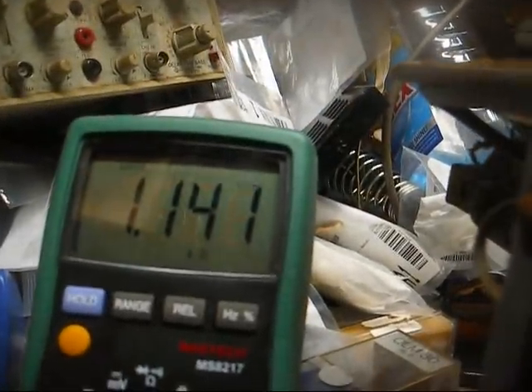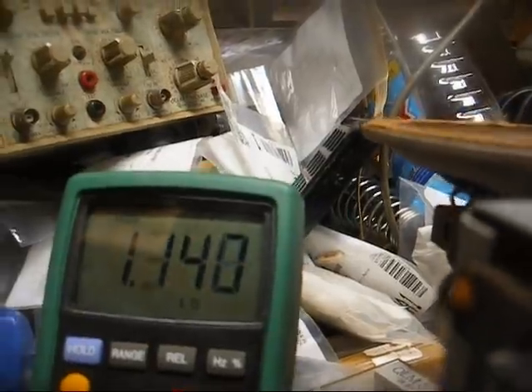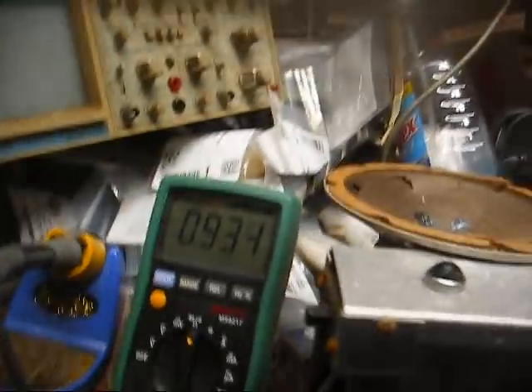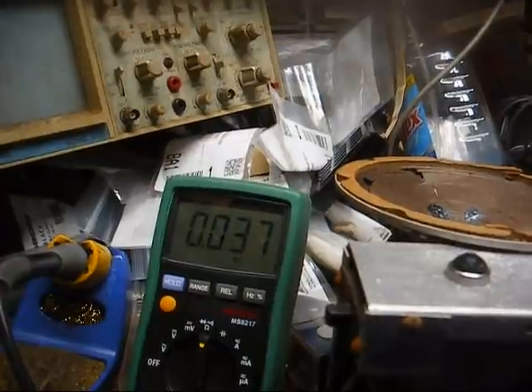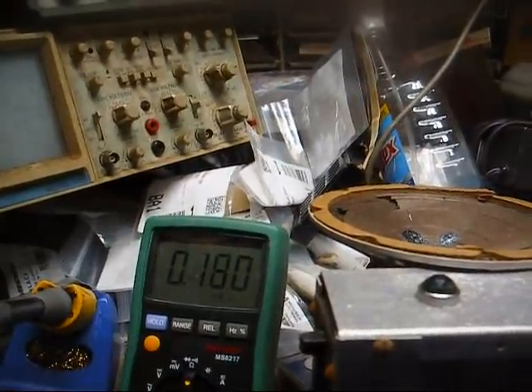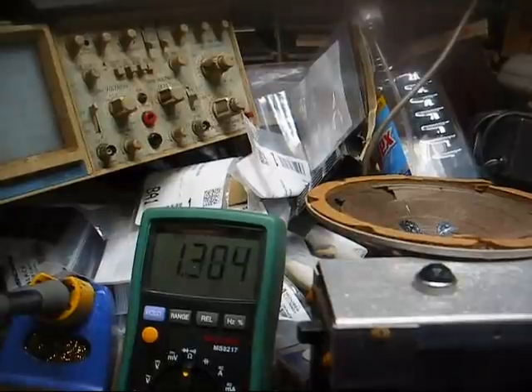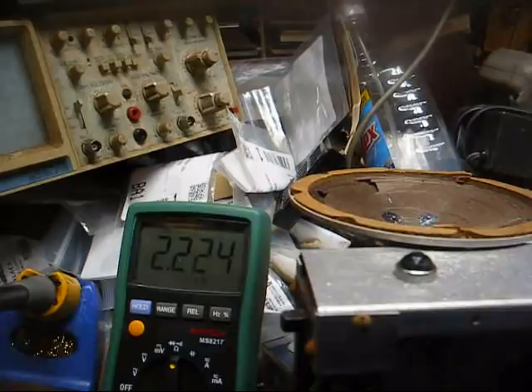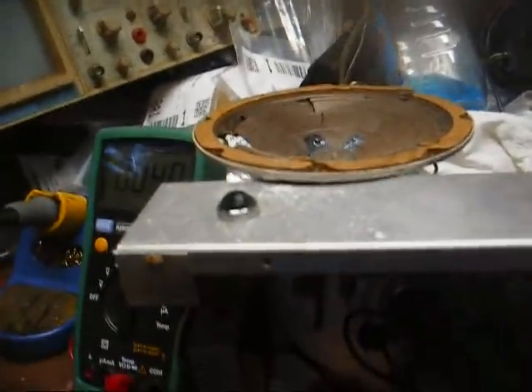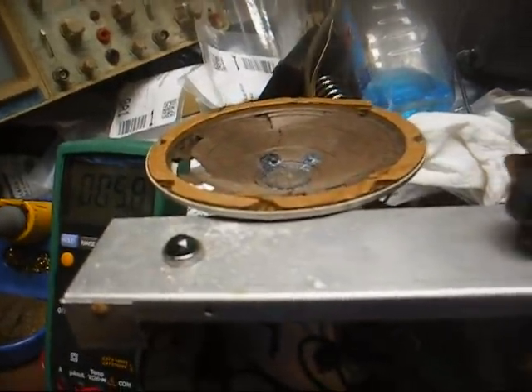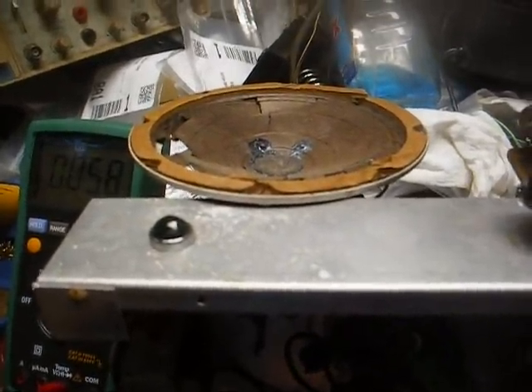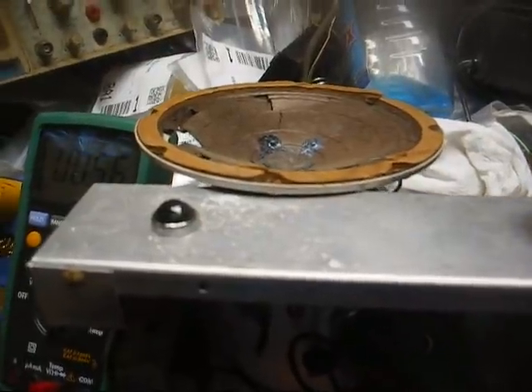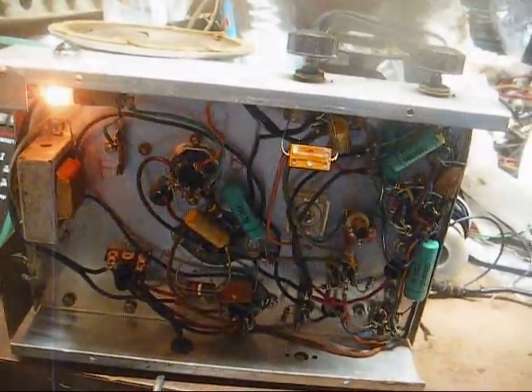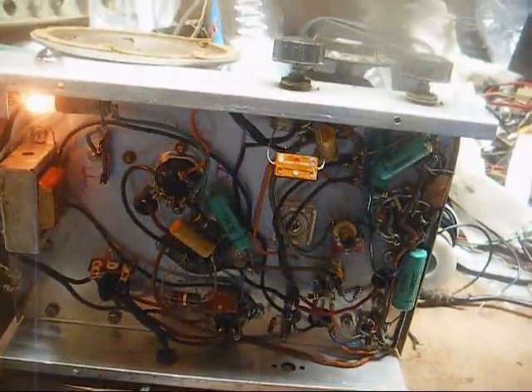I'm reading, it's all over the place, 1.1 k ohms. Alright, I'm going to put some juice to this. Sometimes putting juice to them will cause those contacts to experience a reality check, and they start working better then. Alright, that's good. We now have power. Running about 60 volts AC input.